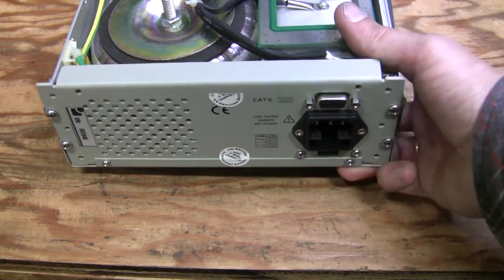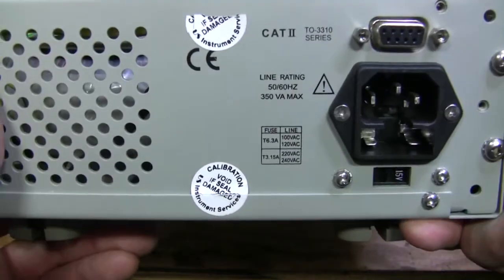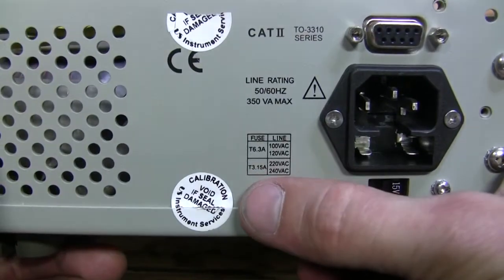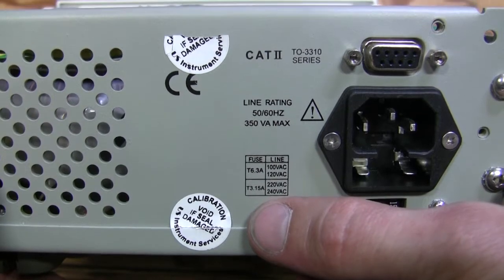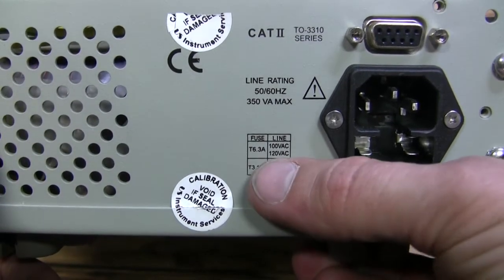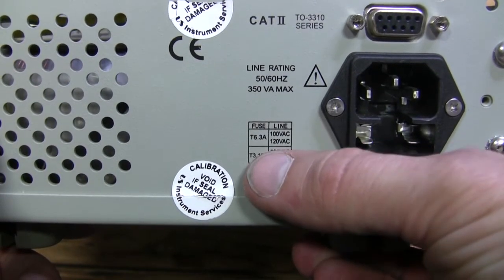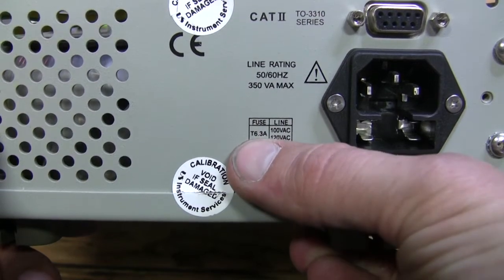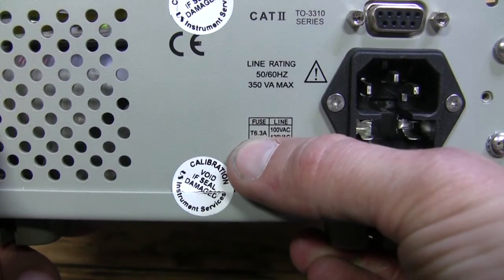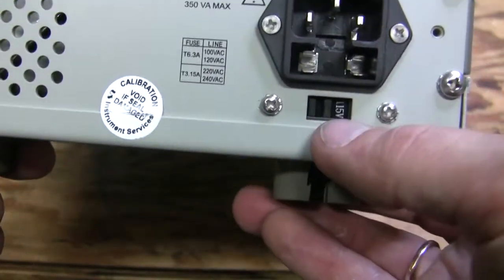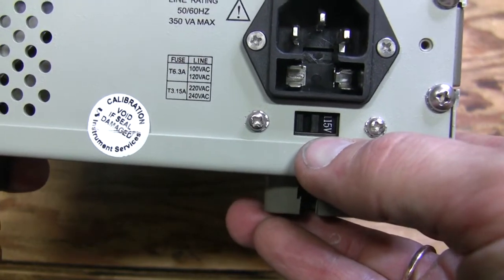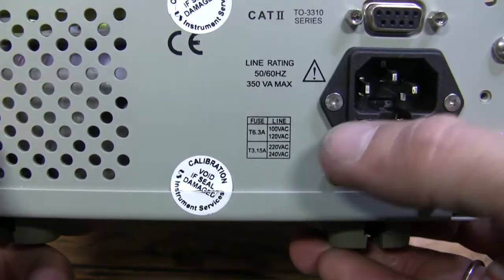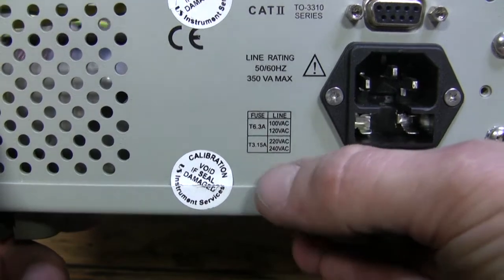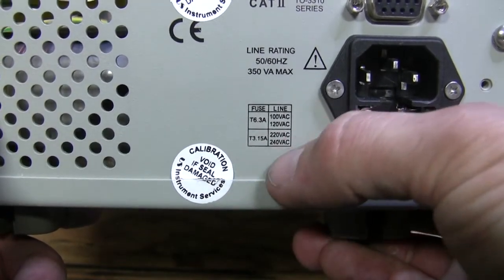Have a look at this. Here's a label on the back saying that for 120 volts, which we have here, the fuse should be 6.3 amps. The voltage is set to 115, which is correct, but the fuse was incorrect, as if it was set for 220 volts.